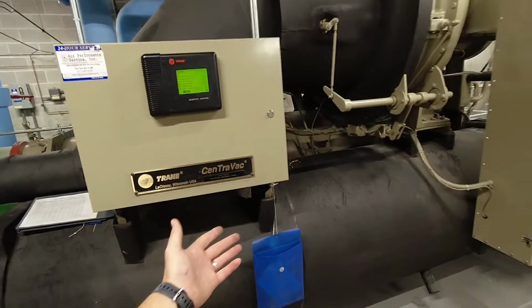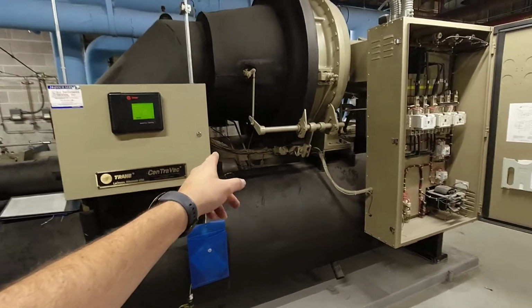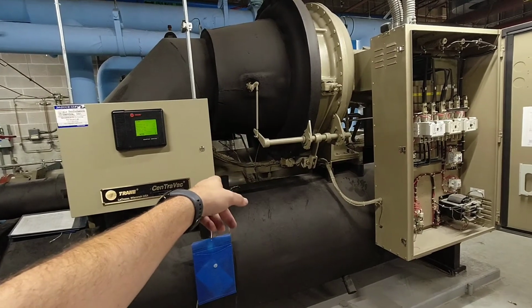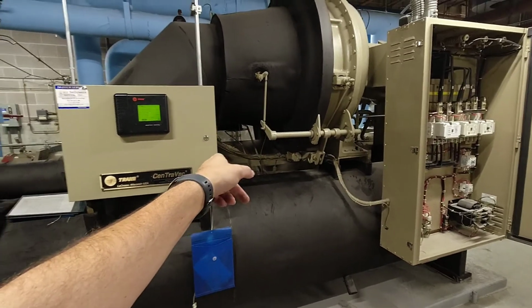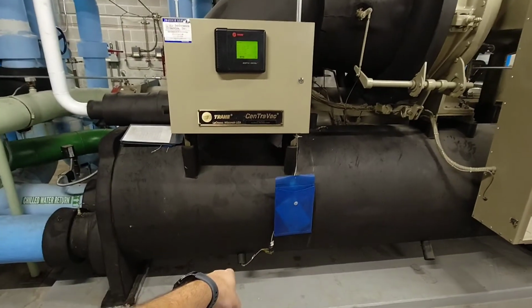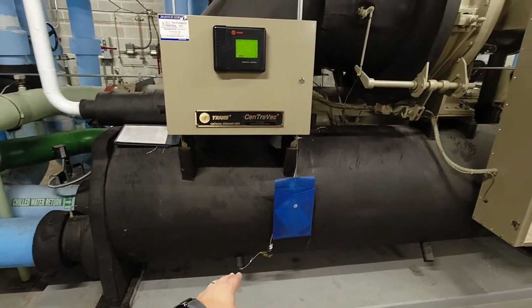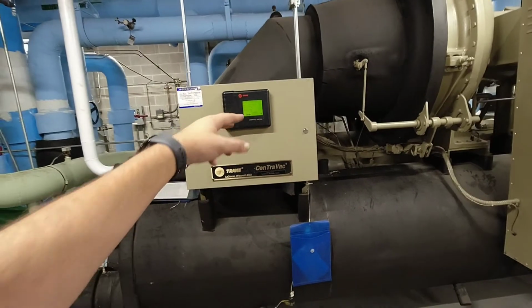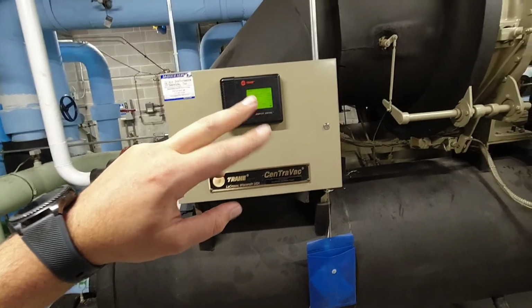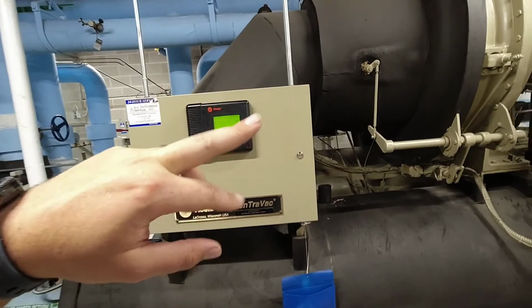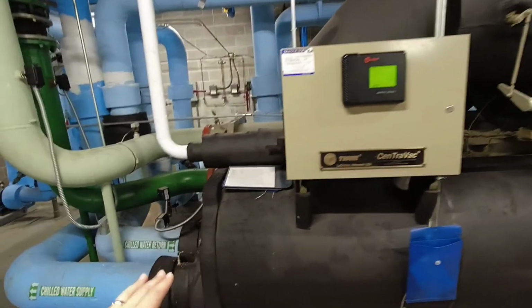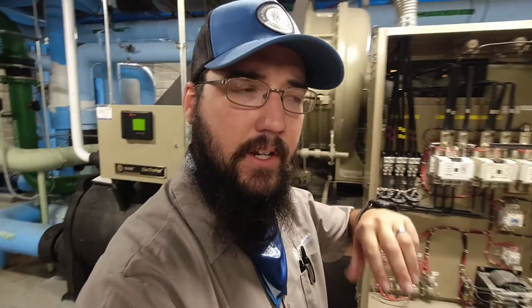So when I do annuals on these, I'll put my gauge on it and compare my gauge saturation to the temperature saturation of the refrigerant, and if they're more than, say, 2 degrees off, I'm replacing them because I'm losing efficiency. So those are your basic components on a CVHE, CVHF series.